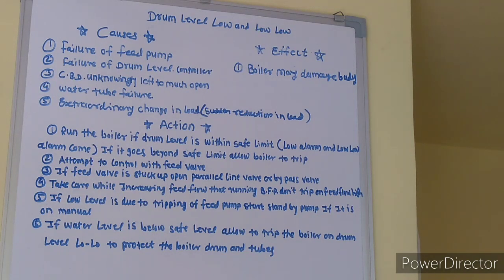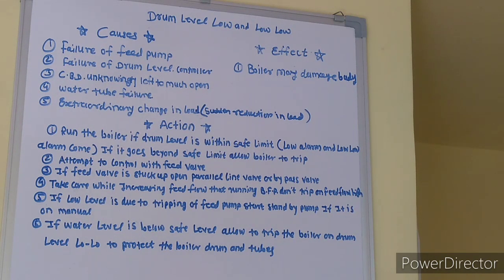If low level is due to a trip in the feed pump, start the standby pump if it is on manual. If water level is below safe level, allow the boiler to trip on drum level low-low, to protect the boiler drum and tubes.